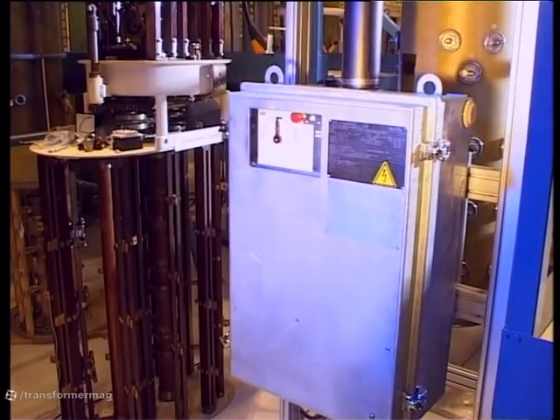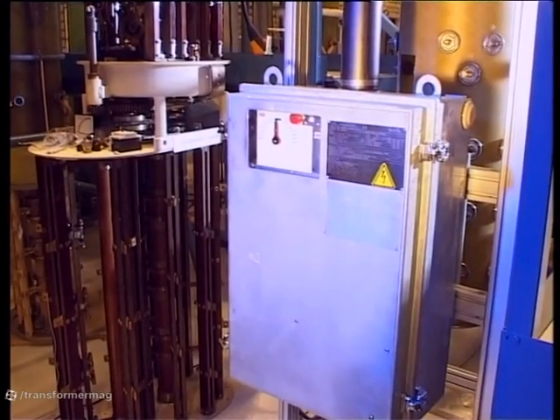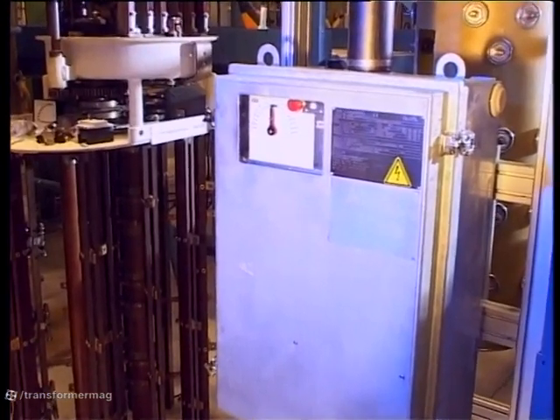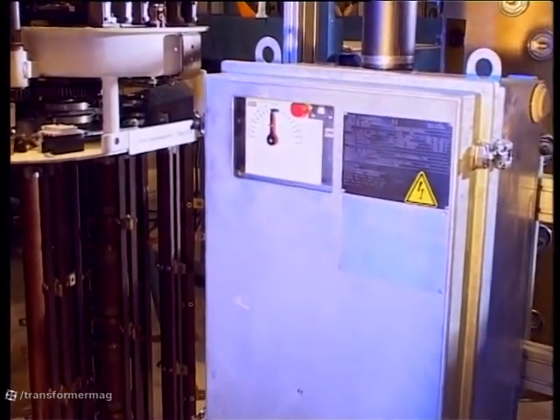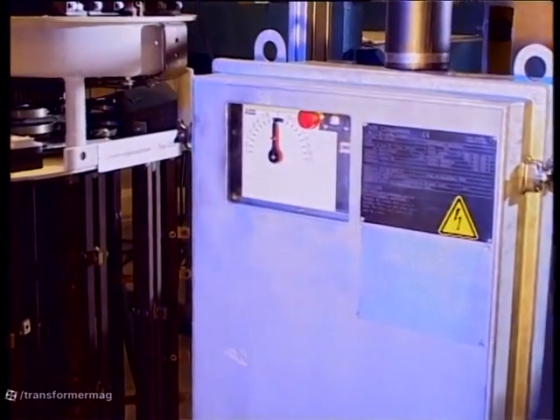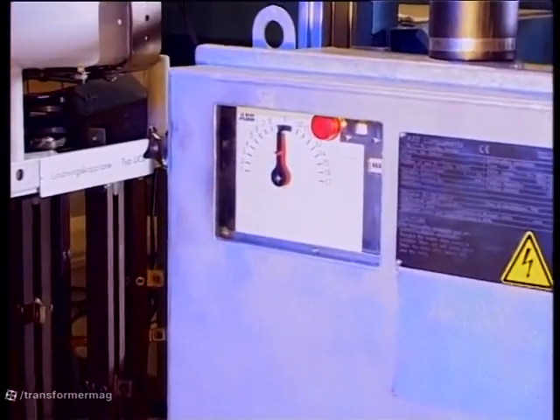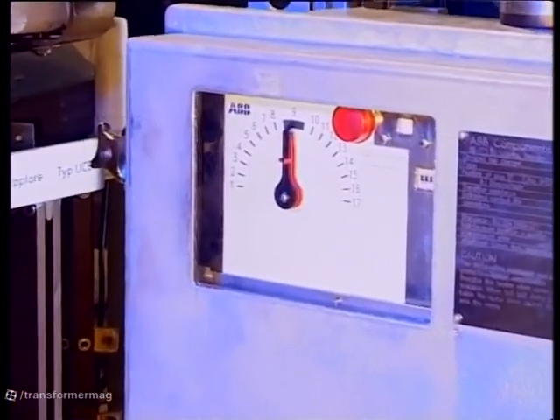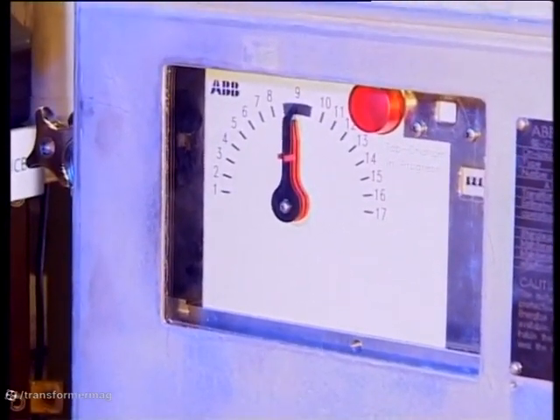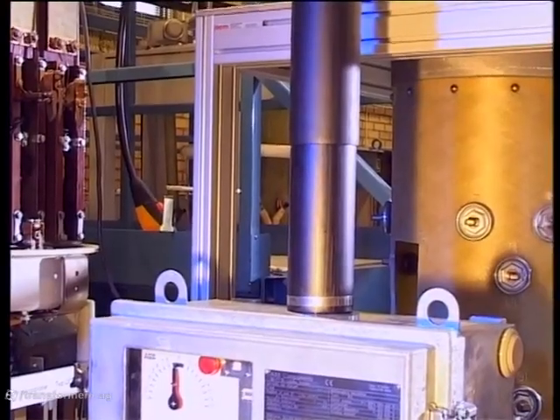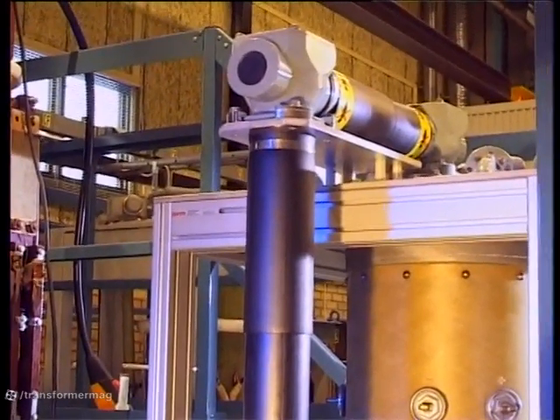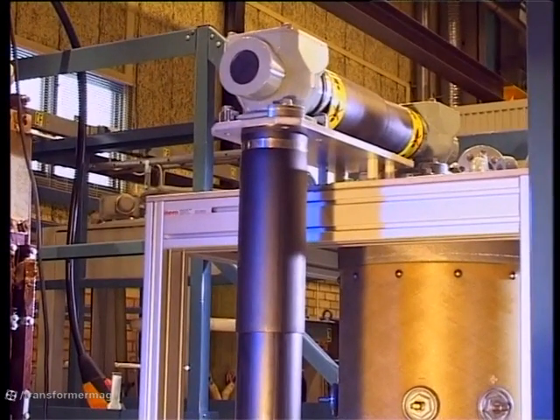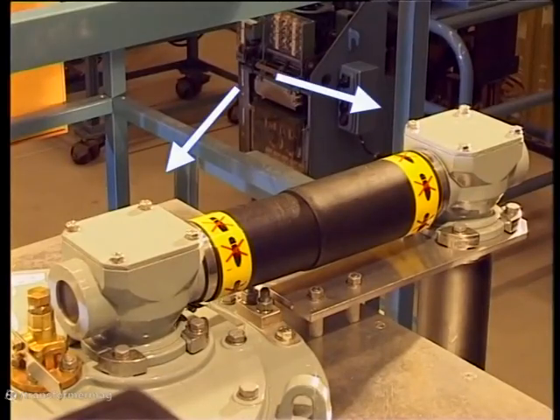This part is called the motor drive mechanism. This is what controls the on-load tap changer. In this maintenance guide, we shall deal with two types, BUE and BUL. There's a vertical and a horizontal drive shaft connecting the motor drive mechanism to the tap changer. The shaft system includes two bevel gears.